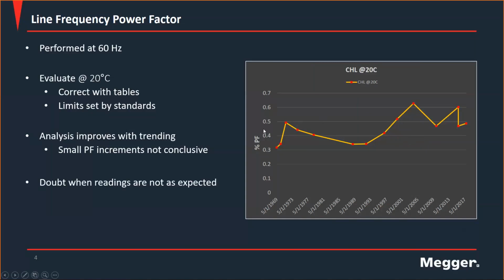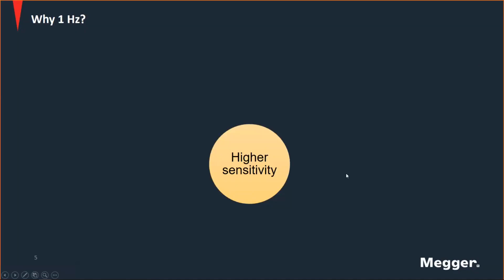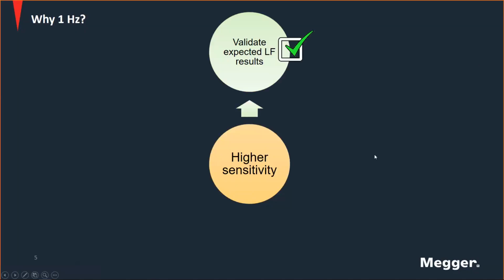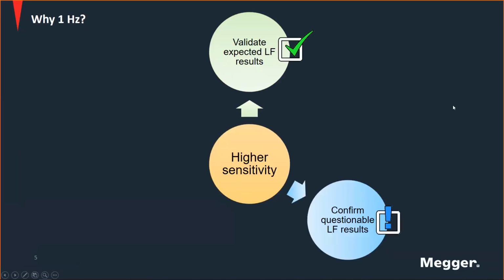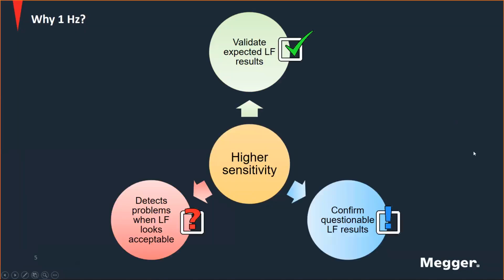Furthermore, when the readings are not as expected, there's a lot of doubt that's introduced. And as I just mentioned, that early deterioration is not noticeable. And then this is where 1 Hertz comes in. There's a higher sensitivity to these early changes. So 1 Hertz can allow you to validate your expected line frequency results, confirm your questionable line frequency measurements, and then finally detect problems when line frequency looks acceptable.